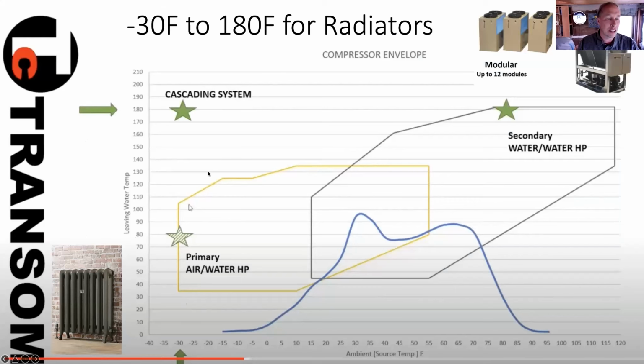Here's an example of a manufacturer out of Canada using a different type of refrigerant. Maybe you don't want to work with CO2 and you want more manufacturers to play with. Okay, well what you need is 2 heat pumps. One is a heat pump that goes down to say -30 Fahrenheit degrees. Totally can get that - this little green arrow is pointing at -30 Fahrenheit. So you get a primary air to water heat pump for cold climates, -30, and you raise that water up to about 80 degrees Fahrenheit. That's the temperature of the water over here. These little loops represent the loop of thermal performance for this heat pump. So you get it at -30, but raise it to 80 degrees Fahrenheit. It can do that job.